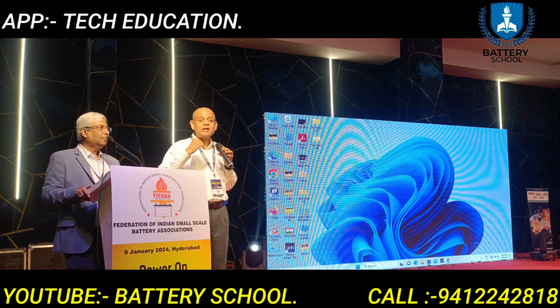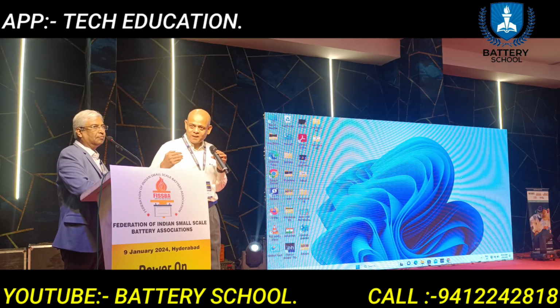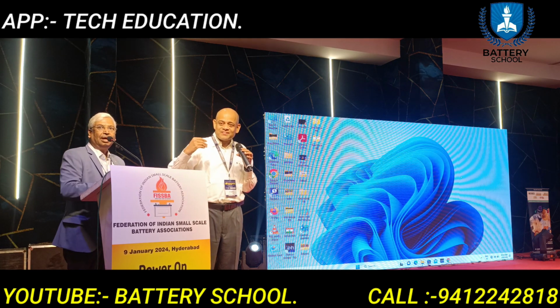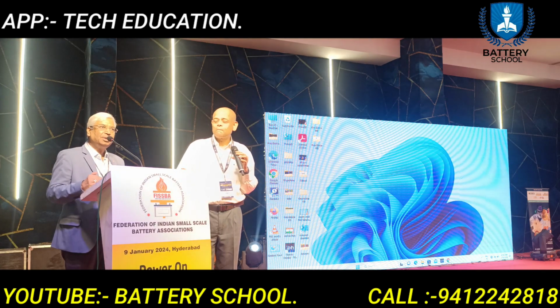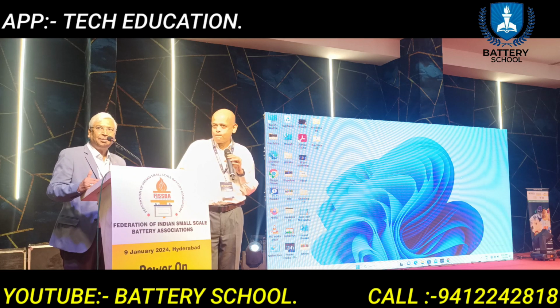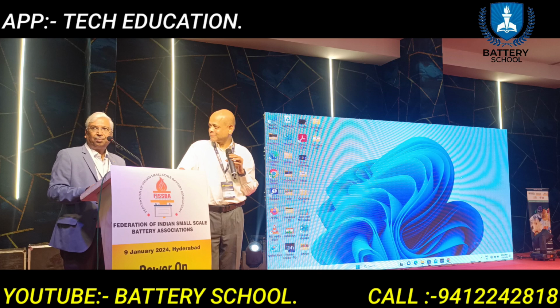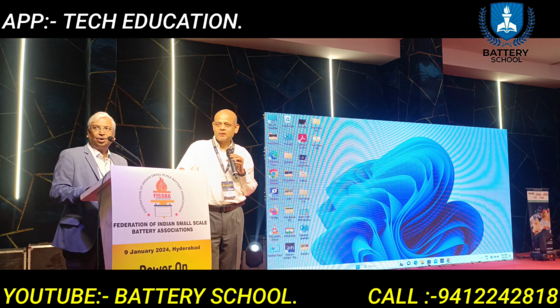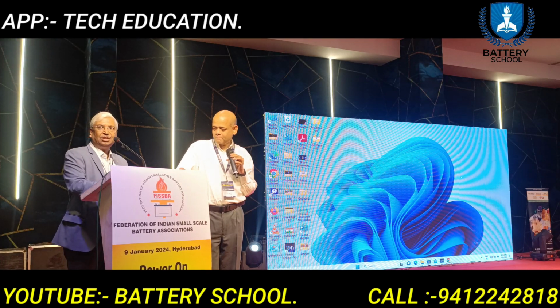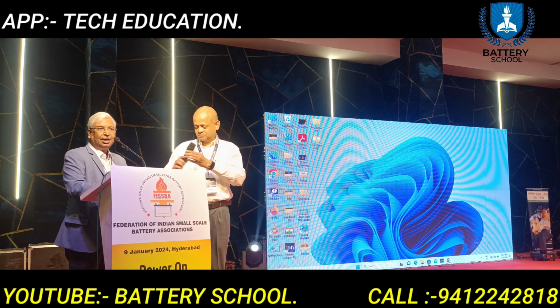See, up to now, as battery manufacturers, we have only been looking at how to make an inverter battery. And certain concepts like cell balancing have come after lithium ion came. There is something known as active cell balancing and passive cell balancing. So these concepts introduced by lithium ion also have to be adopted by lead acid. If you cut off at the proper state of charge, or depth of discharge, and you do the cell balancing automatically using a BMS, then it's very easy.